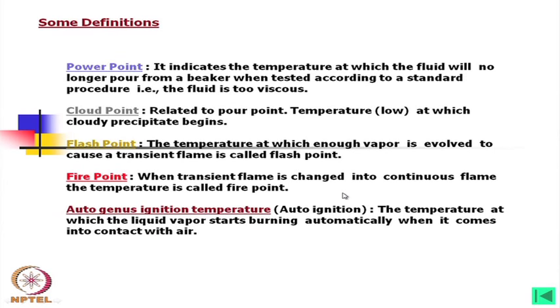That point is called the autogenous ignition temperature — the temperature at which liquid vapor starts burning automatically when it comes into contact with air. After the fire point, vapor will continue to come, and when that vapor contacts the air it will automatically catch fire. This may happen where temperatures are very high, so we have to cool the oil and ensure it does not reach the auto-ignition point.